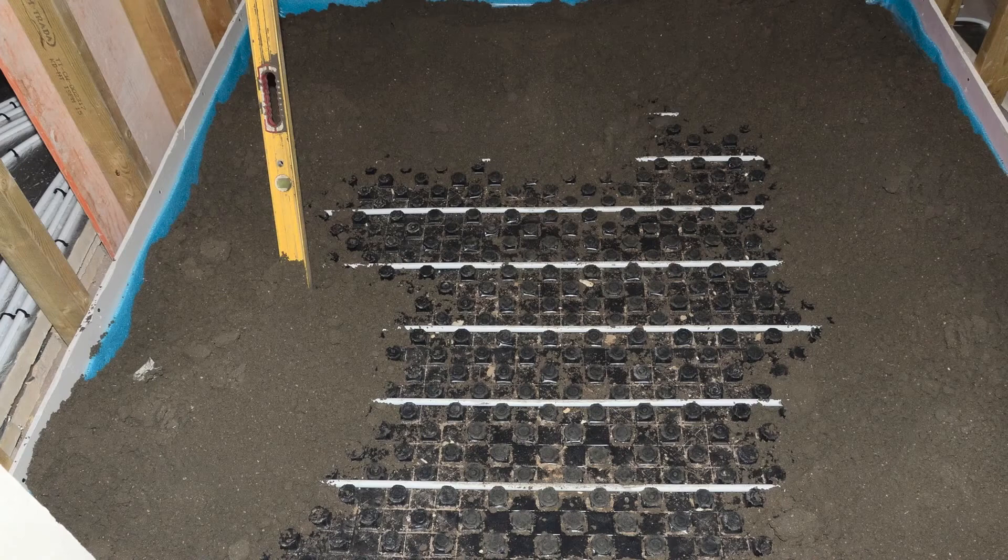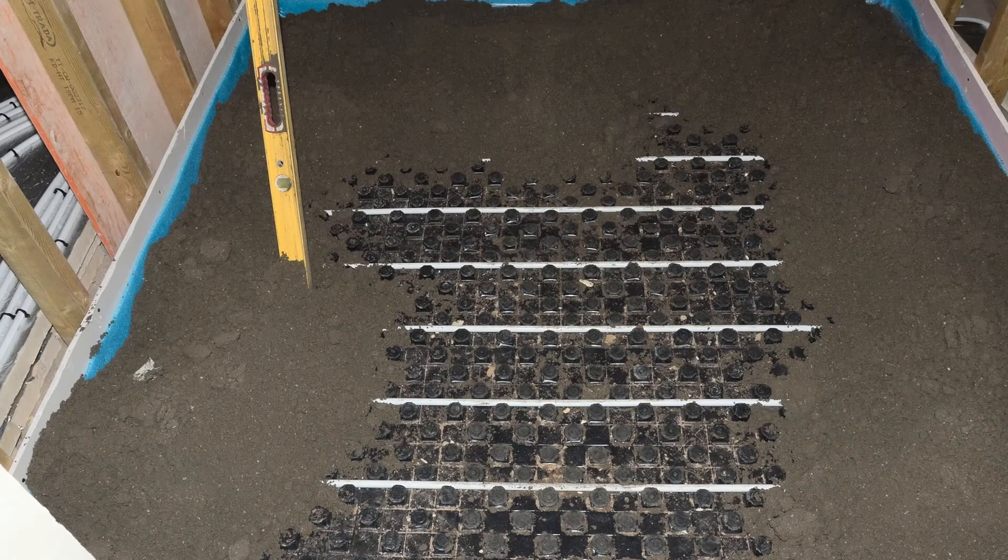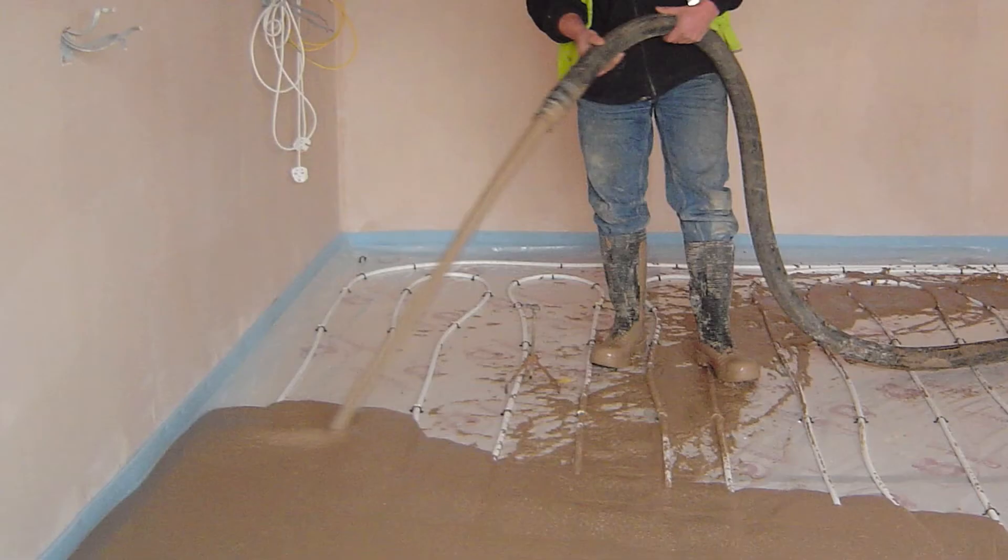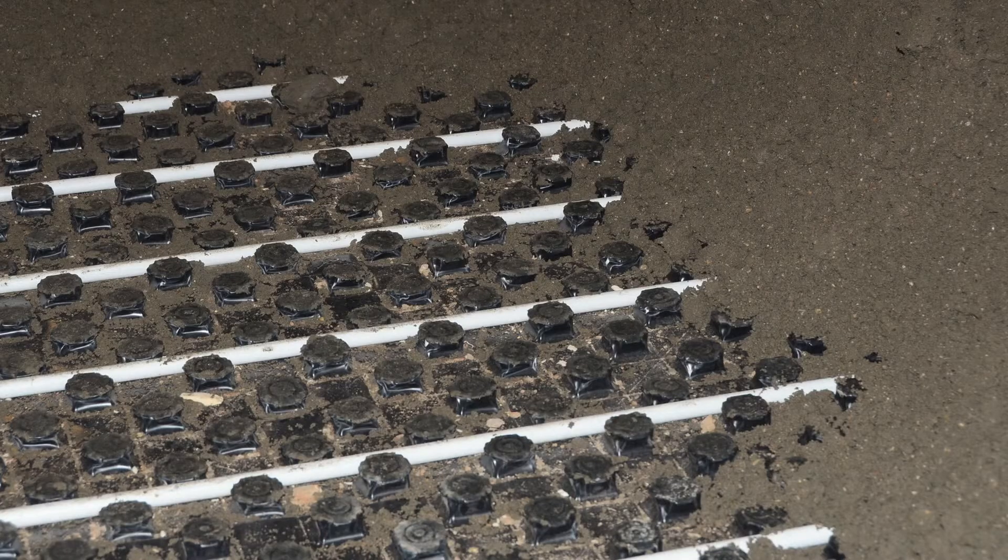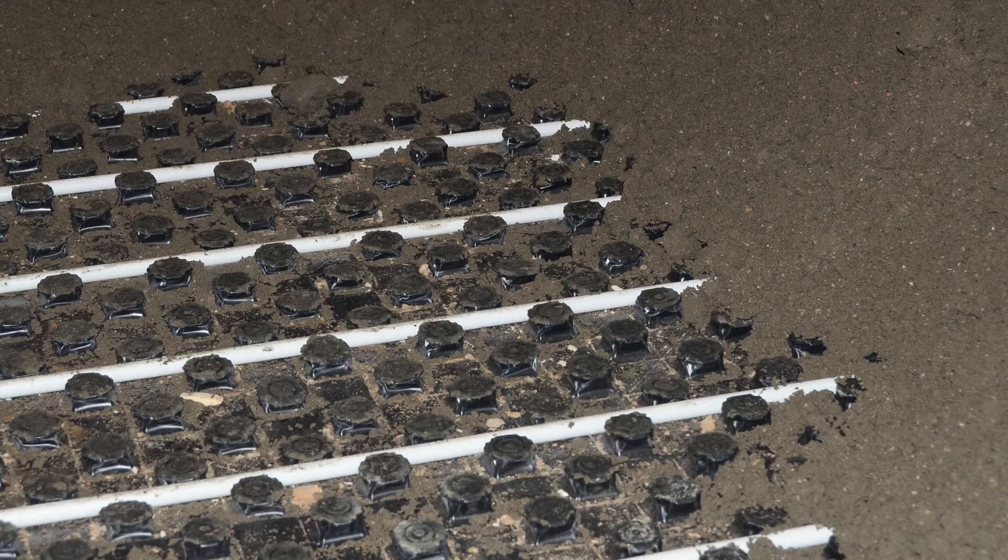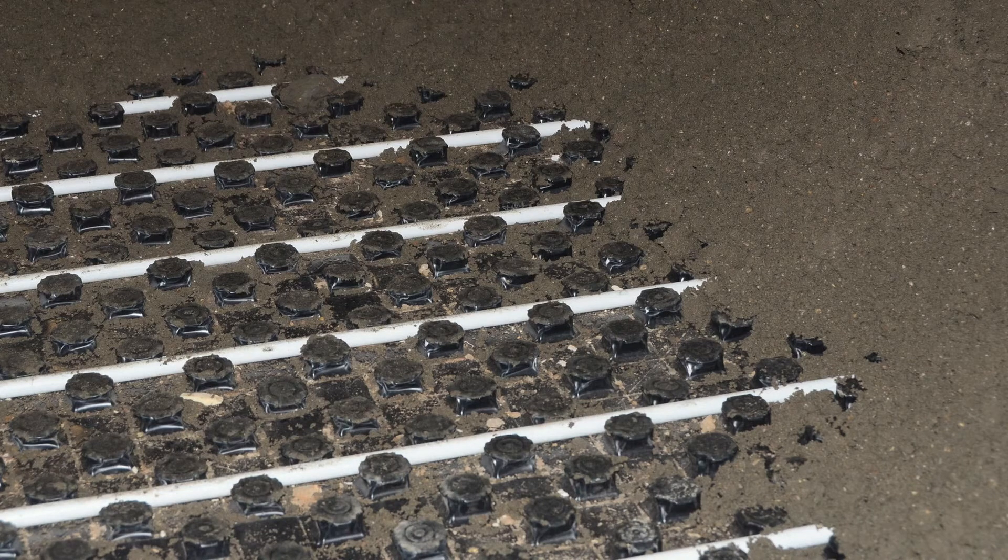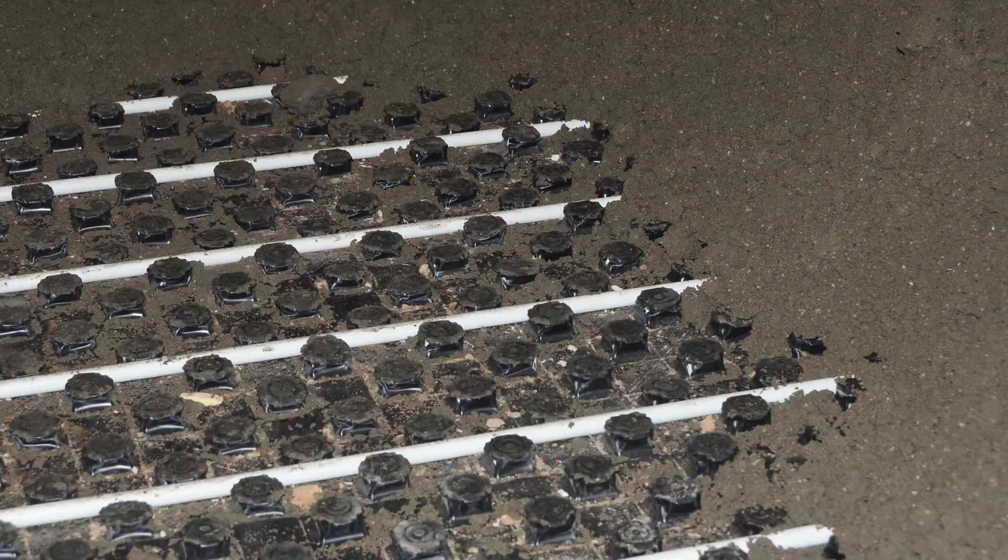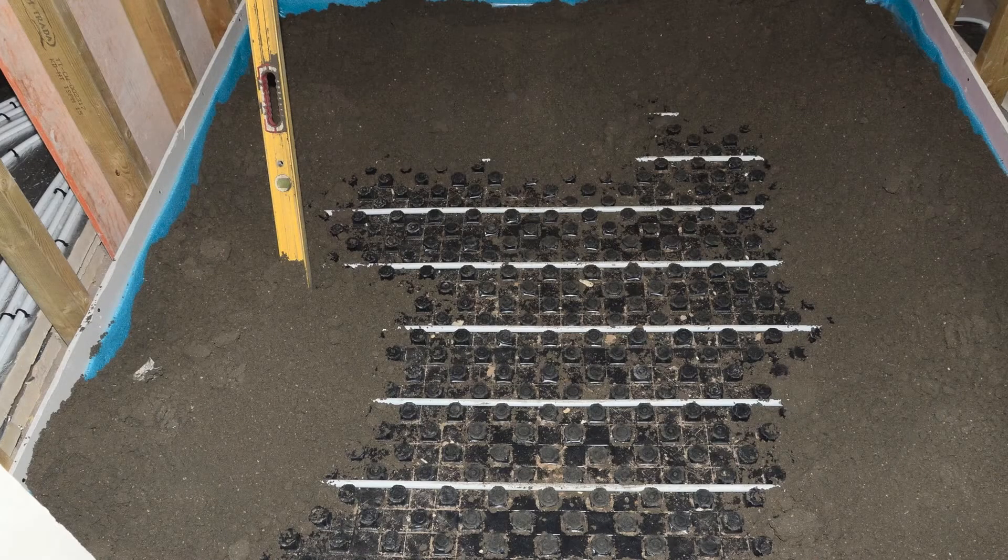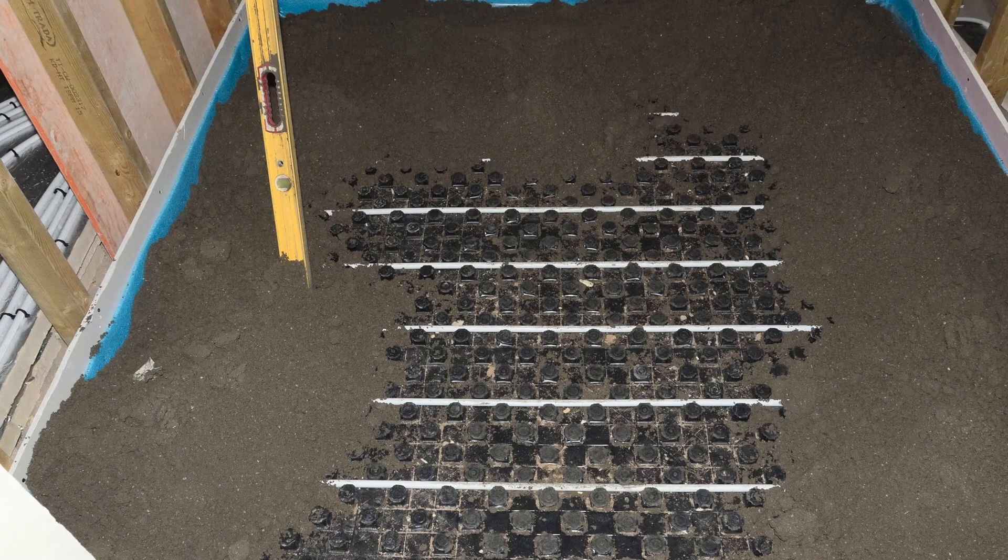A variety of screeds can be used, such as sand, cement or a flowing screed. The screed is typically 50 to 65 millimetres thick. When laying the screed, care should be taken to ensure that the screed is compacted around the pipe properly. Most screeded floors require 28 days after laying before preheating can begin.